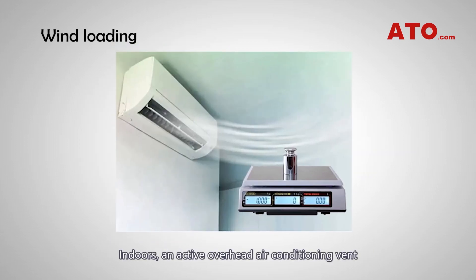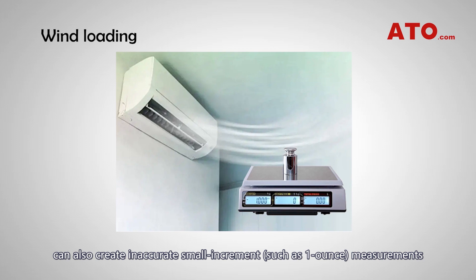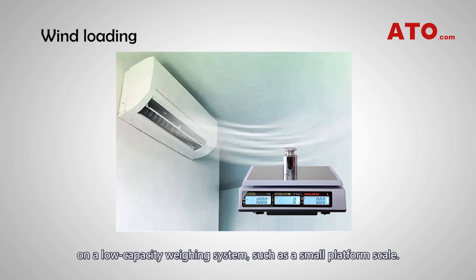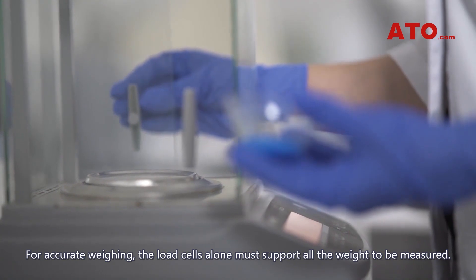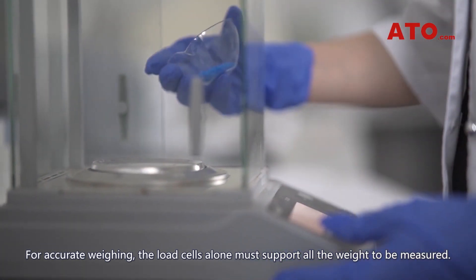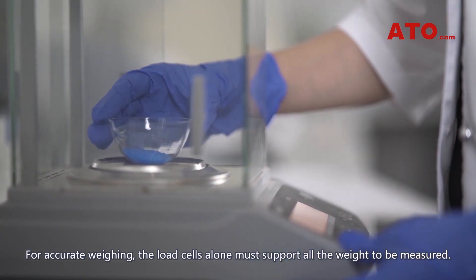Indoors, an active overhead air conditioning vent can also create inaccurate small increment measurements — such as one ounce measurements — on a low-capacity weighing system such as a small platform scale. You can use a plexiglass cover over the platform scale to block or divert the stray air currents. For accurate weighing, the load cells alone must support all the weight to be measured.